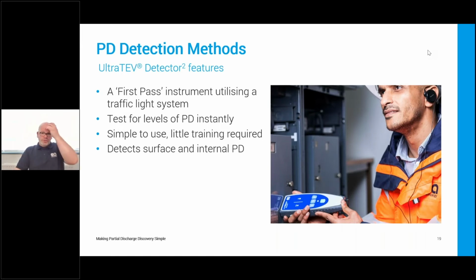So we'll have a little look at the UltraTEV detector first. Basically, as I said, this is a first pass type of instrument, which essentially tells the user if there is PD activity present. It does this using inbuilt threshold levels and utilizes a traffic light system on the display. Pretty basic. Green means no PD activity detected. Amber is low level PD activity detected, so no immediate major issues, but further investigation is needed. And red basically means significant or high levels of PD have been detected, in which case it's probably time to leave the area and some urgent further investigation will be needed.